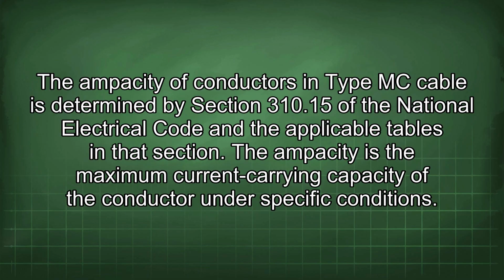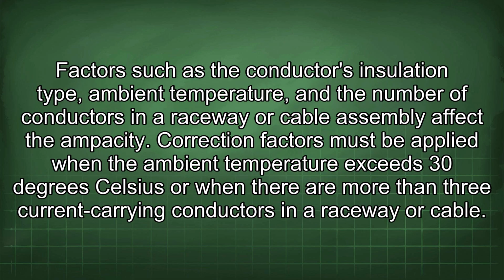The ampacity of conductors in Type MC cable is determined by Section 310.15 of the National Electrical Code and the applicable tables in that section. The ampacity is the maximum current carrying capacity of the conductor under specific conditions. Factors such as the conductor's insulation type, ambient temperature, and the number of conductors in a raceway or cable assembly affect the ampacity. Correction factors must be applied when the ambient temperature exceeds 30 degrees Celsius or when there are more than 3 current-carrying conductors in a raceway or cable.